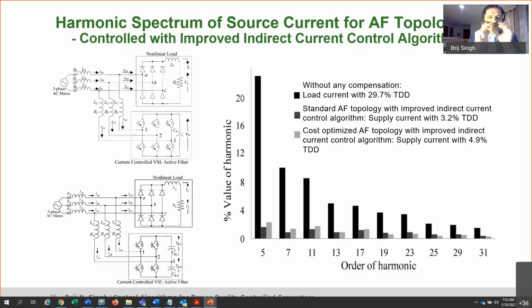You have to have a little bit of resistance, but it's not like there are design tricks and all that. There are a lot of papers on that. So you could go after the 5th and 7th harmonics and reduce them to minimal, and then your next concern starts at the 11th and 13th.